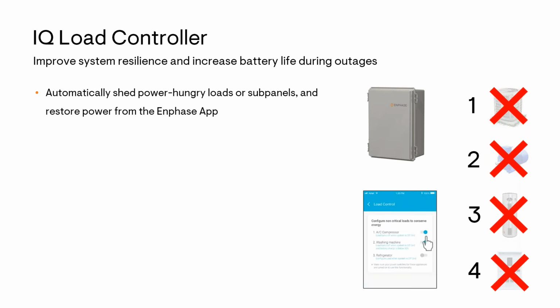So what does it do? With load control, a homeowner can make sure that specific large loads, which could potentially overload the microgrid and shut it down, or potentially drain the batteries very quickly, would get turned off immediately when the utility grid fails. And then the homeowner with the Enphase app can actually manually restore power to these devices if they want to.